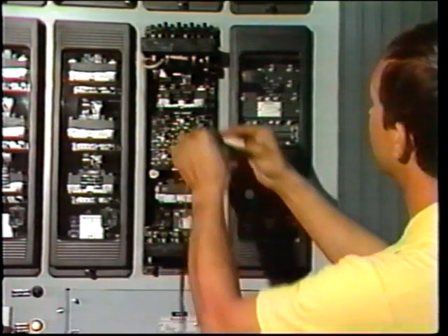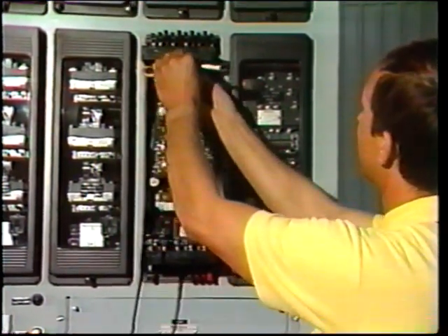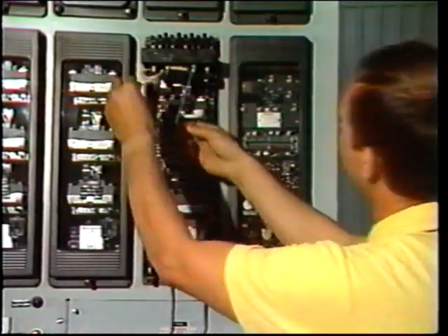We already pointed out in the last segment that some items of equipment, high-voltage transmission lines, for example, cannot always be taken out of service to permit routine testing of protective equipment. But we still need to carry out the testing to assure that the protection schemes will operate correctly when needed. In this case, we have to carry out the tests with the line in service carrying load.